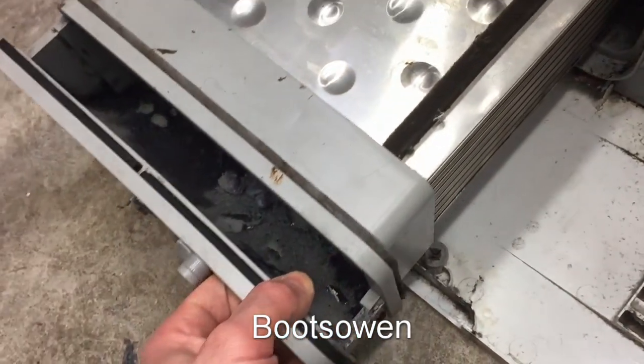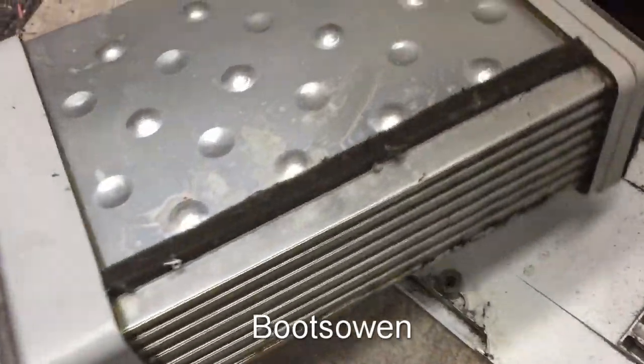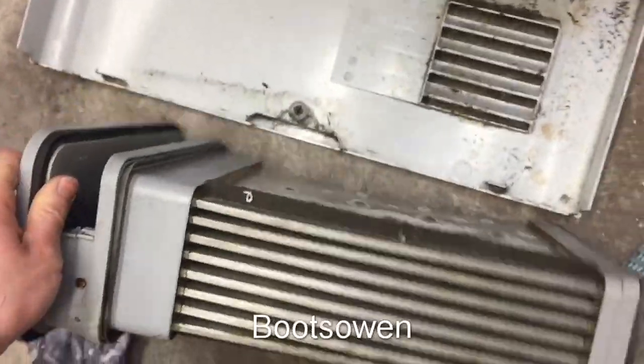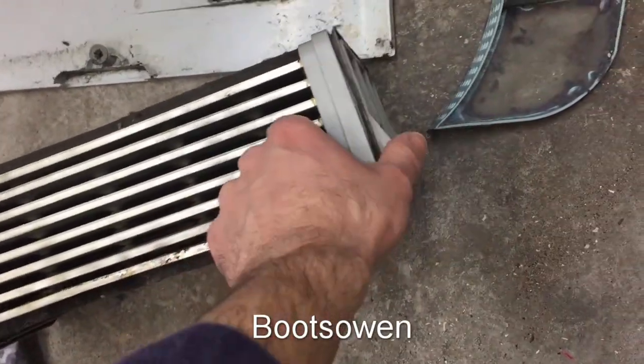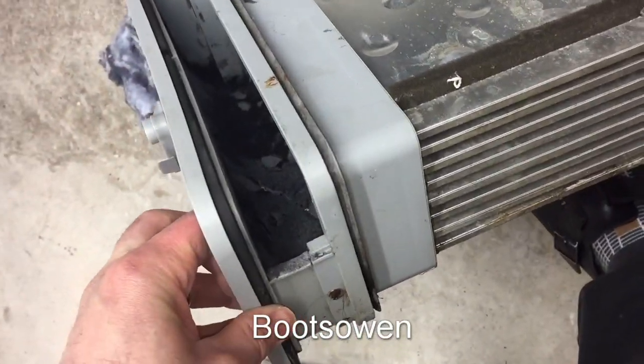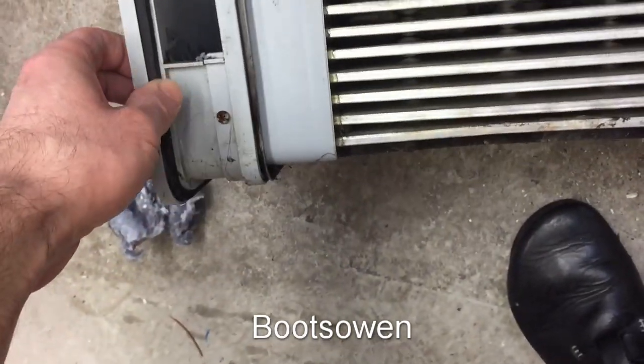You can see in here it's pretty dirty. But there is a passageway through all of those aluminium plates to let air move, so this one isn't so bad. I posted a video a couple of years ago of cleaning one of these and it was completely clogged — the person who owned it thought it was broken, but it wasn't broken at all, it just wasn't clean. You pull that out, look at it, and think yeah it's clean this way. I'll give that a wash — it's pretty clean on the back, but the front needs a bit of cleaning.